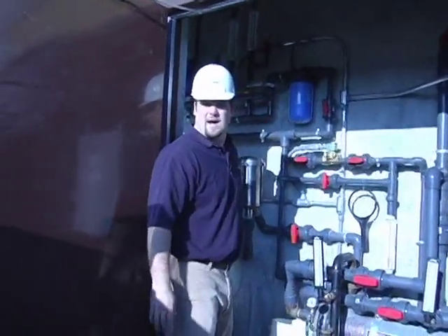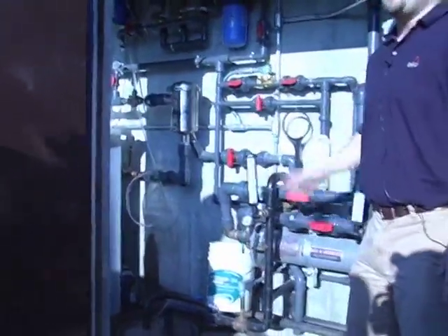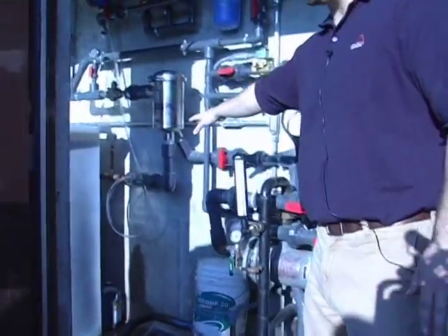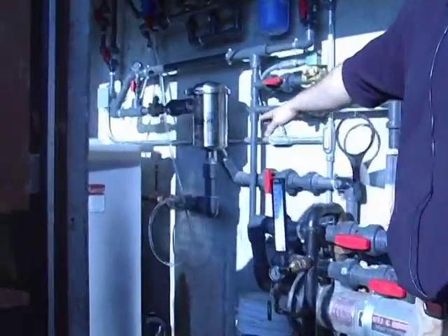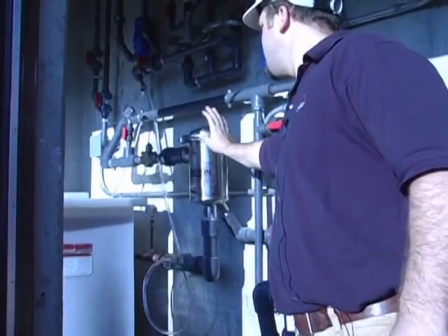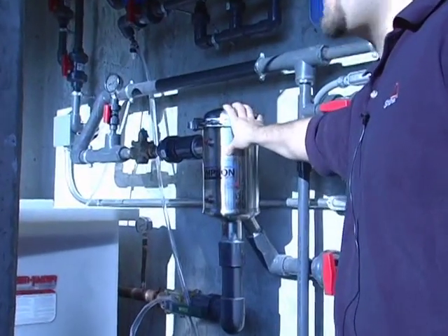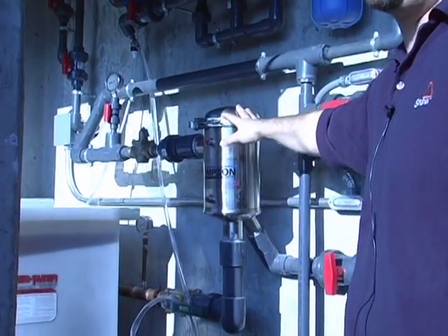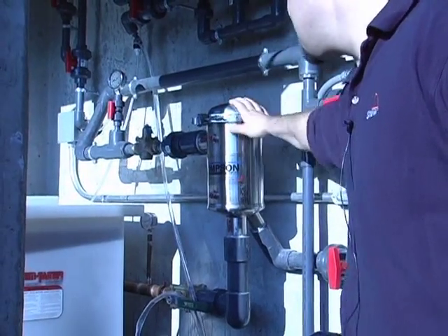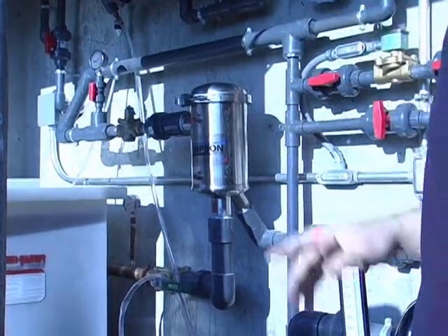All right. Coming from behind this, this is kind of hard to see, but this is the nutrient tank. Coming from behind this tank, you see your main water feed coming in this copper piping. It's going through this filter. This is the 120 mesh filter that protects the system from the suspended solids when the plant water starts being used. This is removable, and there's a basket in there that can be cleaned and taken out.